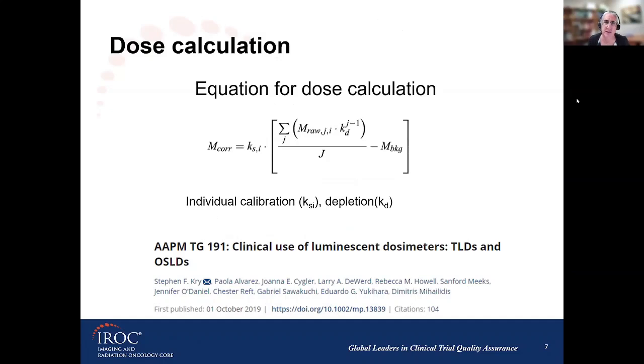So important things regarding getting this uncertainty and this control scenario is coming in the way that the corrected reading is calculated. So this is, again, an equation coming from 191. This corrected reading requires the knowledge of a background. In the case of the IROC system, and based on the reading we were using, background is negligible. The OSLD system gives you the possibility to take multiple readings, and so the final corrected reading is going to be coming from an average of readings.